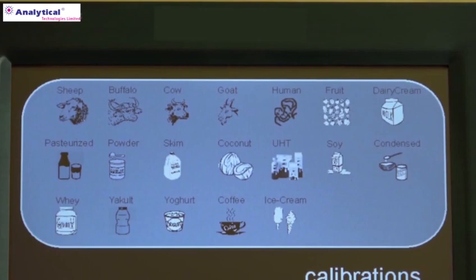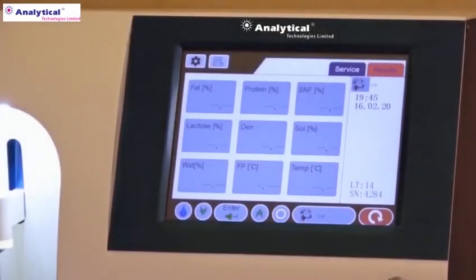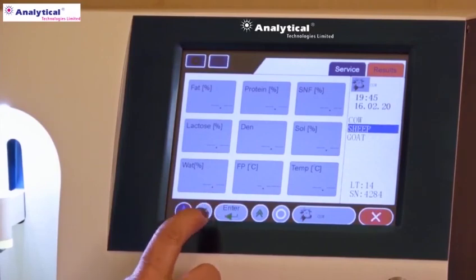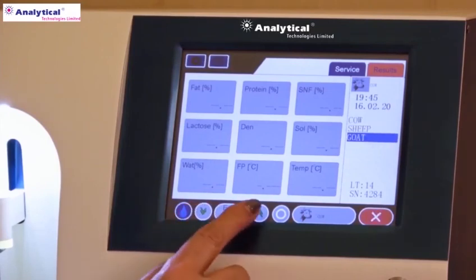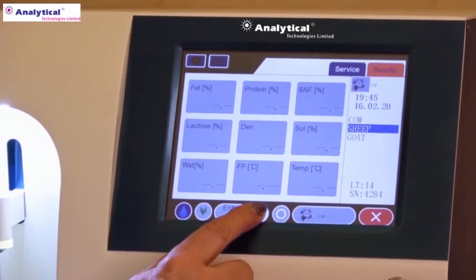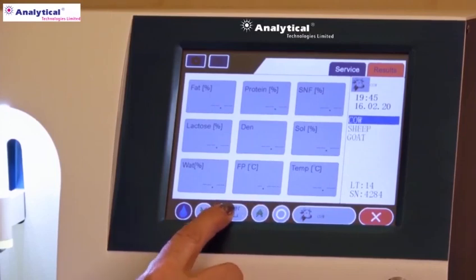It's worth noting that after calibration the unit can analyze cream and ice cream mixtures without having to water down the products. The unit can be calibrated for up to 3 products at a time. If you want to switch between already existing calibrations, press once enter and the display will list the 3 existing calibration banks. Use the up and down arrow buttons to select a calibration and press enter to confirm.